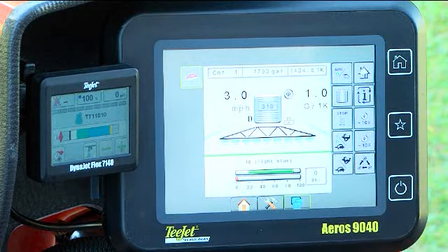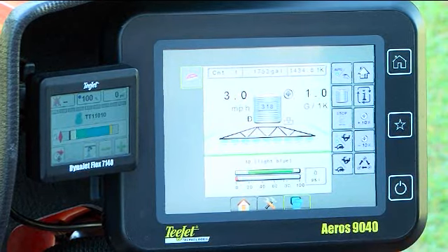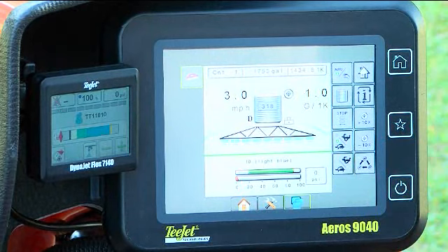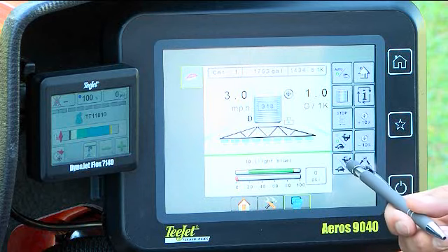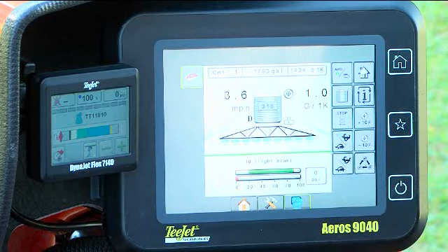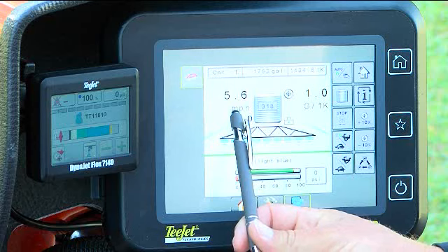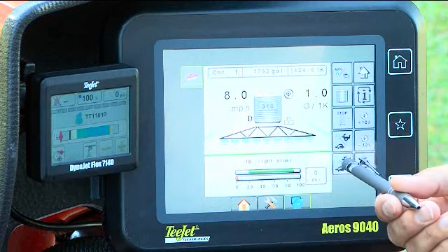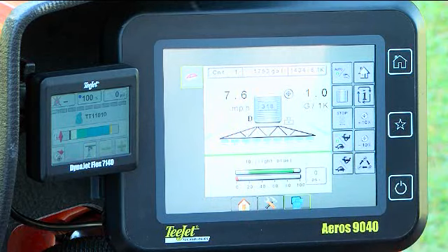By touching number 5, the bottom one on the left, it will switch between the high and low simulated speed. The simulated speed setting will then be displayed on the main screen to the left of the tank volume when enabled. Again, it's really important for us to reinforce that when performing a manual calibration, ensure that you are not in an open job from the main screen, as it will not work. If you don't get flow in simulated speed, that's typically the reason.